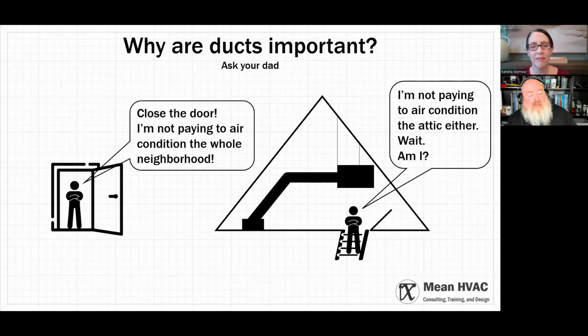The other reason ducts matter is it's how the cooling and heating get to your room. If the ducts aren't large enough to accommodate the airflow needed, you won't get the air there. A lot of contractors are taught, and if you research online, you'll come across something called a ductulator, or duct sizing calculator, that basically tells you if you have this much air, you need this size duct. That's not how that works, like at all.